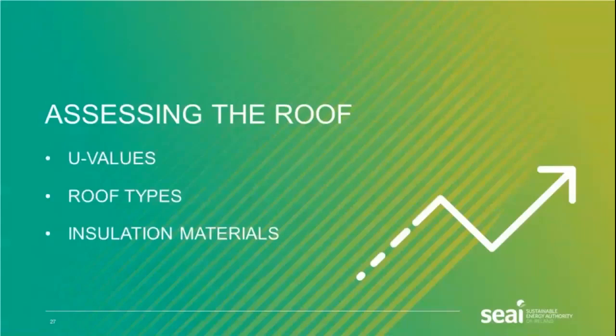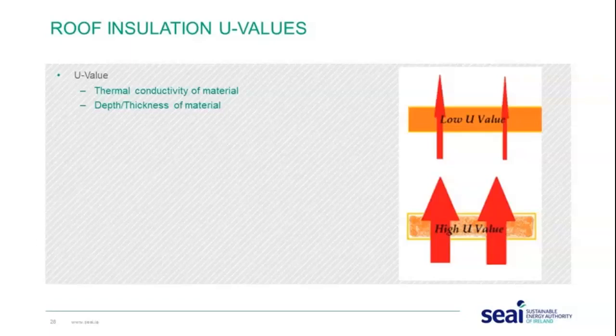We're going to move on to assessing the roof — in particular, U-values, roof types, and insulation materials. The U-value is determined by the conductivity and the depth or thickness of the material being used. The lower the U-value, the less heat transfers through that product; where you have a higher U-value, more heat transfers through.